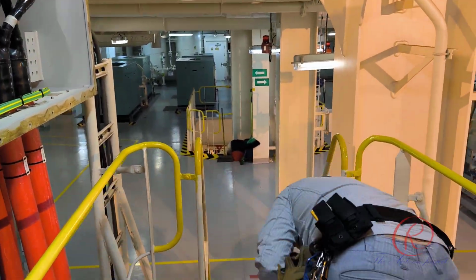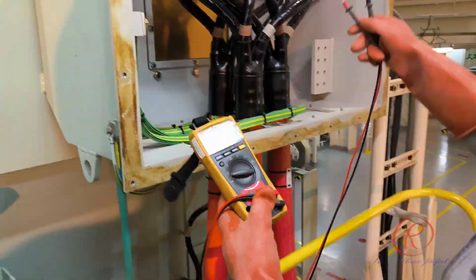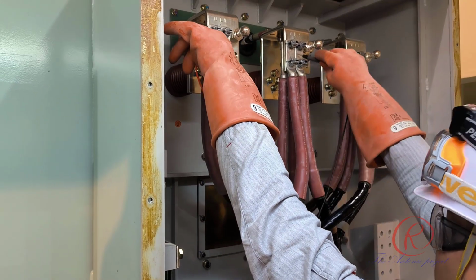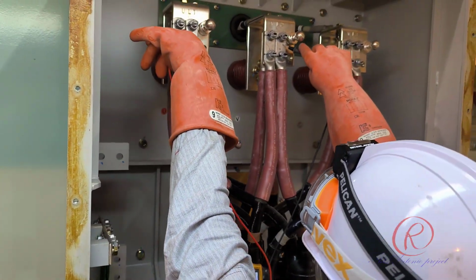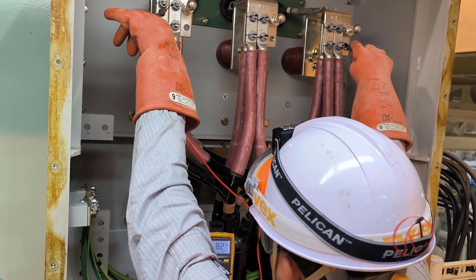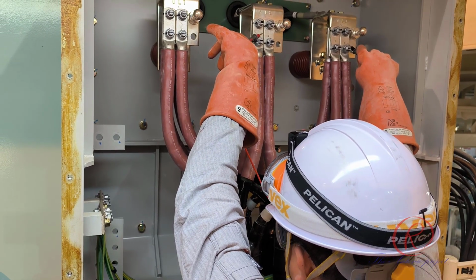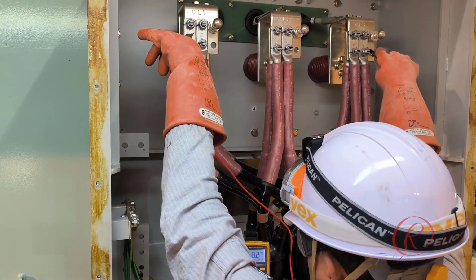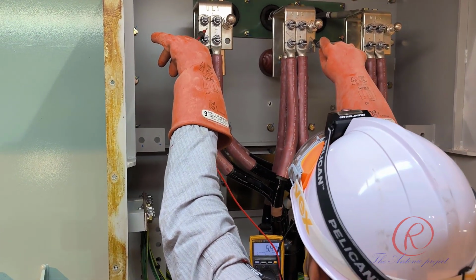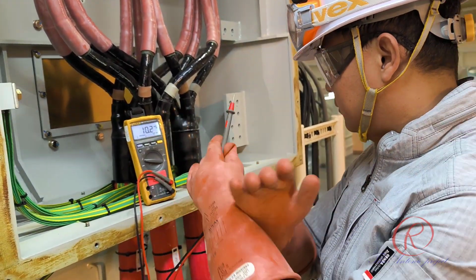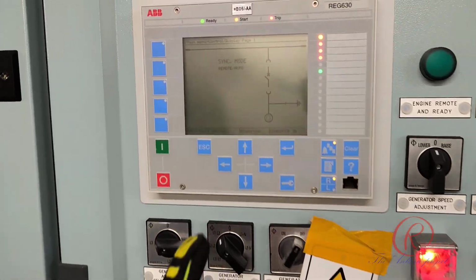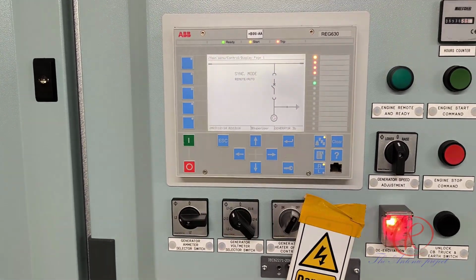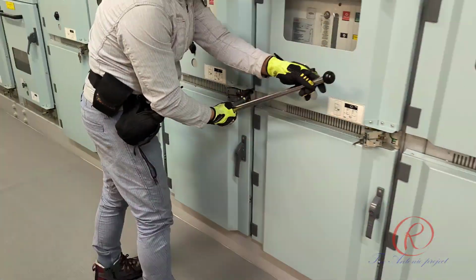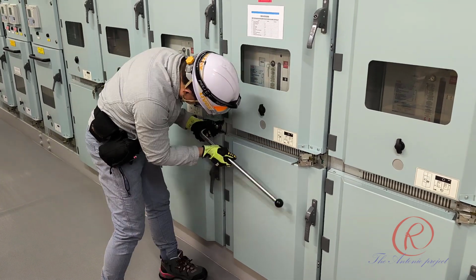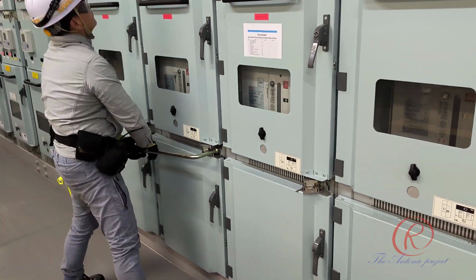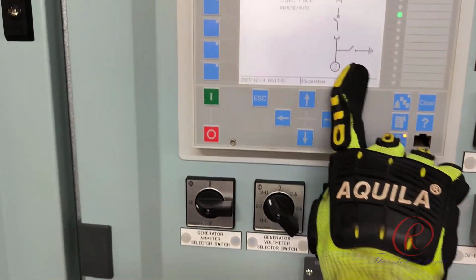Carry out a double check of the terminals for any power source using a multitester. Measure the power on the terminals. Double check the existence of electric power. After confirming that there is no power source at the alternator terminals by high voltage detector and multimeter measurement, it is safe to proceed to the next steps. Next step is to release the earthing. Confirm that the earthing is already released.